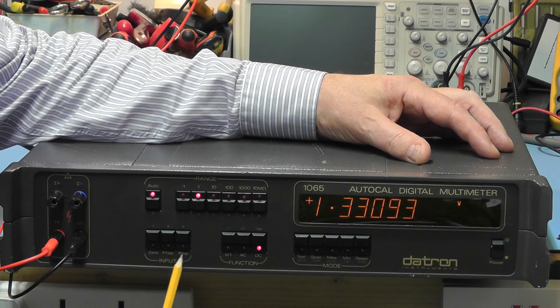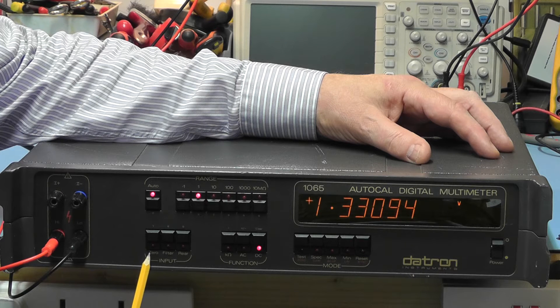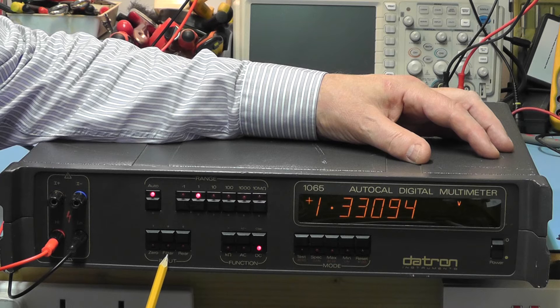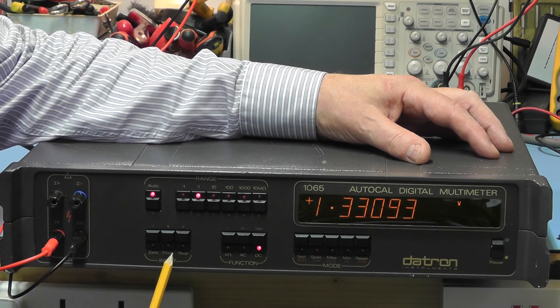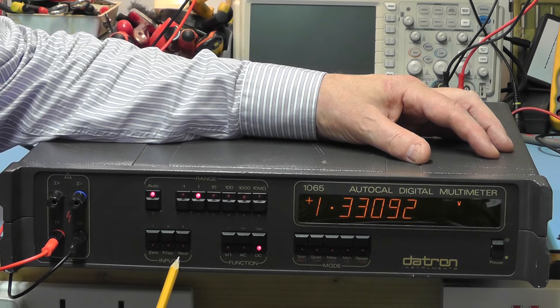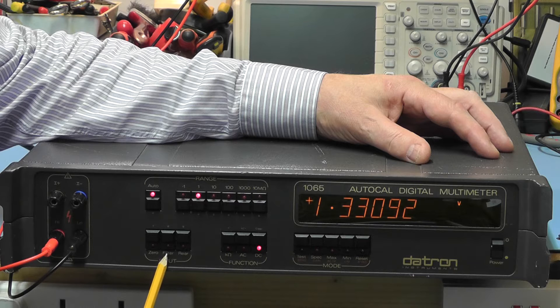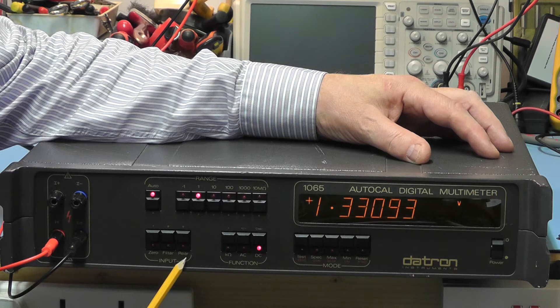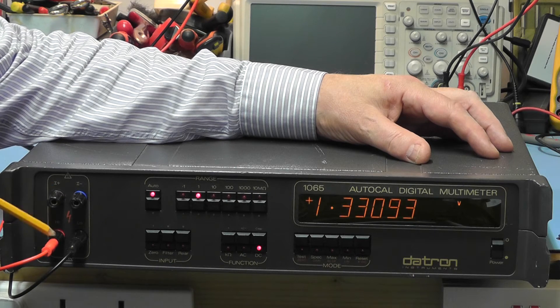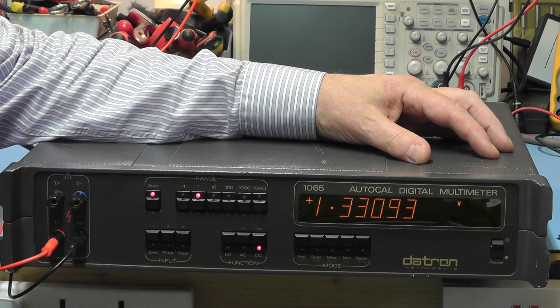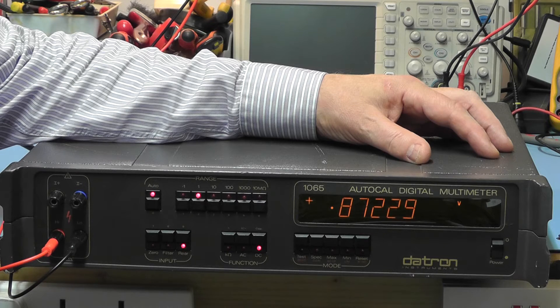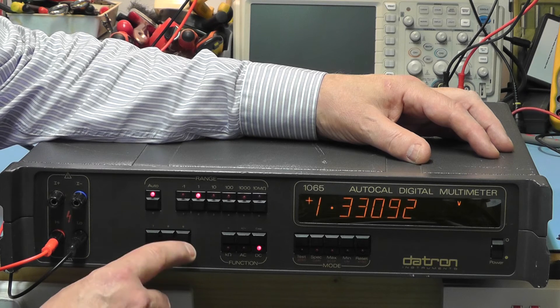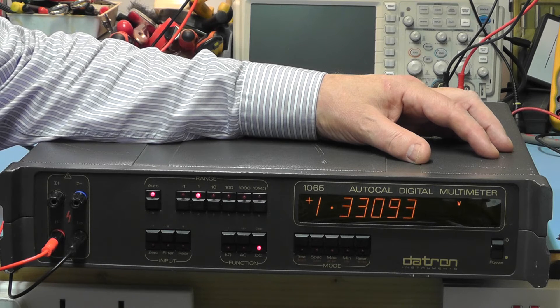The other buttons down here: the zero button, we have a filter button which is used on the AC range. It's recommended that if you are reading AC signals which are lower than 360 hertz then you activate the filter. We have another button here which switches the input leads from the front to the rear of the meter. Pressing again returns it back to the front.